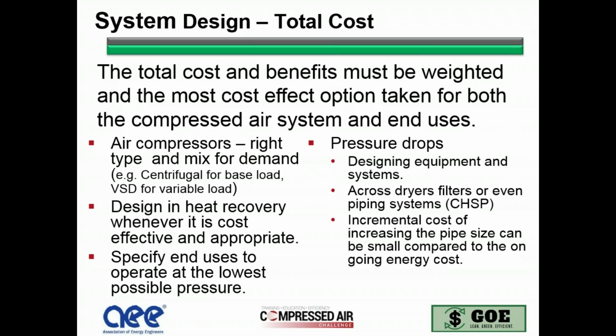Looking at what those are, not only when it's designed, but then after time, because systems are always engineered great in industry, but then I find they grow over time, and it's not always engineered after that. So you have to watch what happens over time as well. Many times in the past it was acceptable to have pressure drops of 5 to 10 pounds through a large system. That's really not acceptable because, again, you're talking about large systems and large costs. Over time, it's very cost effective, and you'll find that many times the pipe size can be increased for a small amount of the cost, and that gives you a much better pressure drop through the entire system. And it gives you ongoing energy efficiency and cost savings.